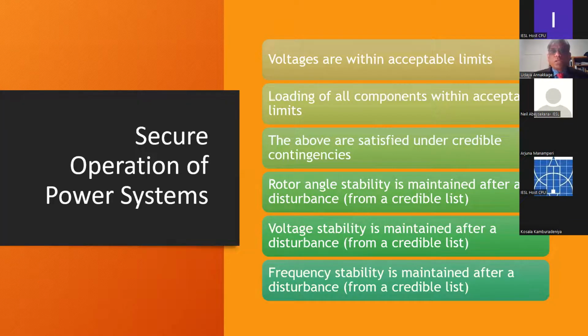So for secure operation of a power system, just summarizing, one has to check whether the voltages are within acceptable limits, and the loads of all components are within acceptable limits. So we are talking about the current operating condition. And if you are happy with that, then you have to check whether these conditions are satisfied under credible contingencies from the list of contingencies that I talked about. Then for each stability category, rotor angle stability, you have to check whether the rotor angle stability is maintained after a disturbance from a credible list.